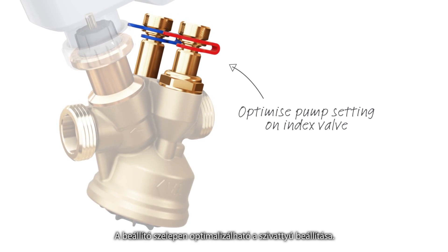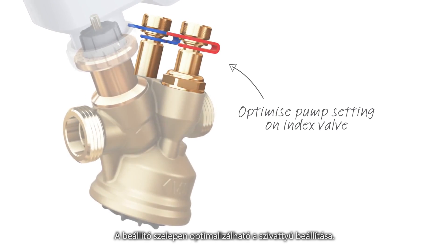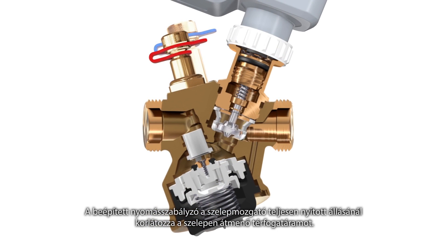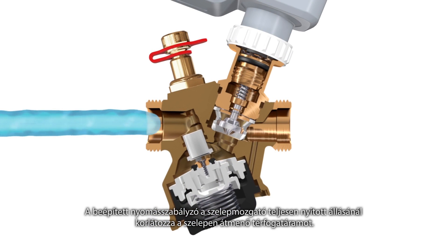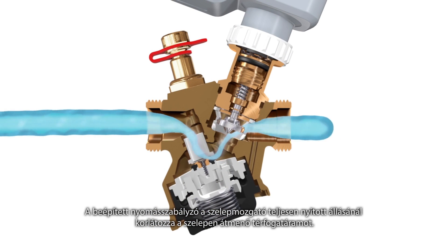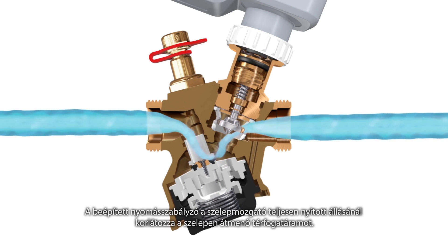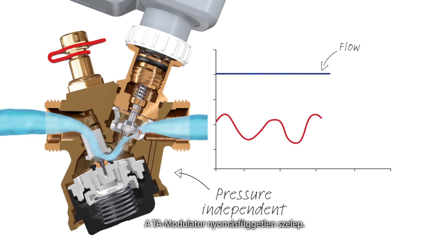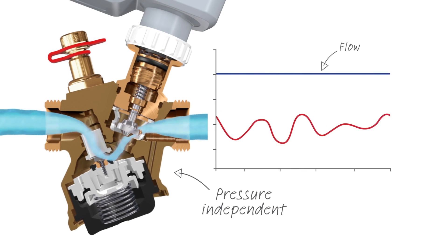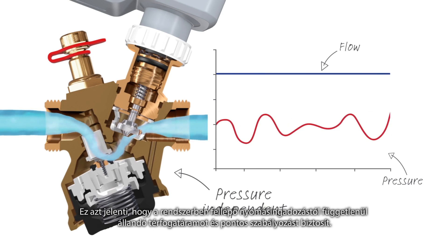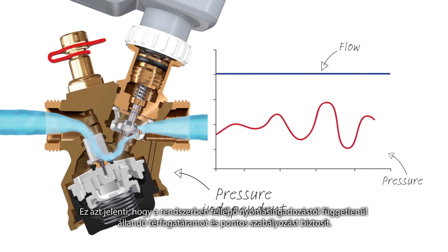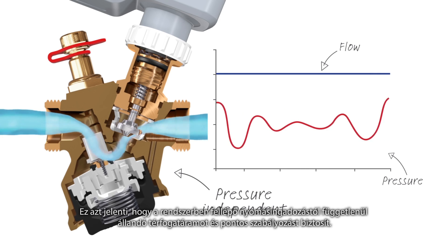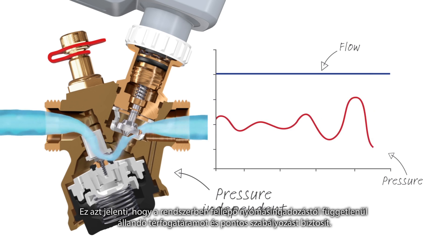On the index valve, you can optimize pump setting. The built-in pressure controller limits the maximal flow through the valve when the actuator is fully open. TA Modulator is a pressure-independent valve — it keeps the flow constant regardless of pressure fluctuations in the system and guarantees high control authority.